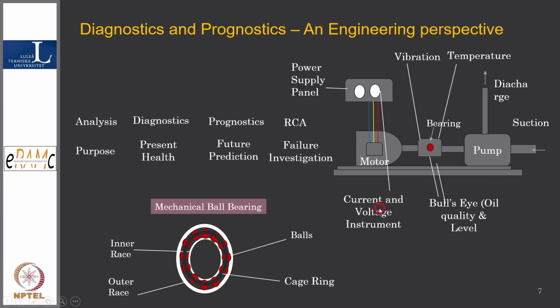Sometimes motor current signature or voltage variation, a dip in voltage and all, also provide critical information about the health of the motor. So what we have seen here is prognostics and health management or diagnostics of motor, bearing and pump, and of course the piping and all that, and this motor current signature analysis we have.